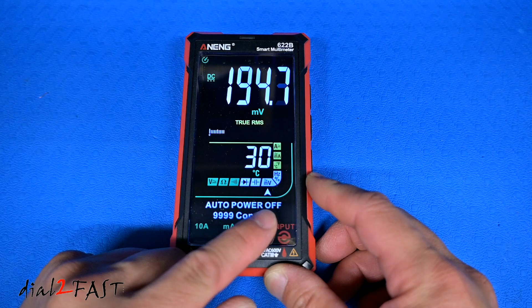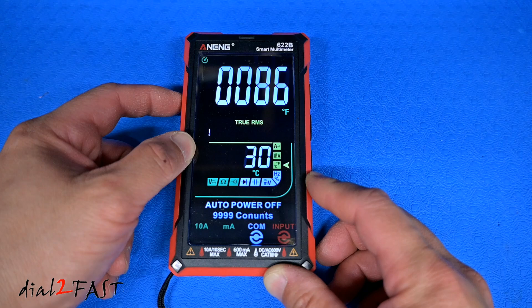If you press the select button on the side, you can switch over to measuring continuity, diode, capacitance, DC millivolt. Press it one more time and now we'll measure AC millivolt. With millivolt measurement, it will measure up to 600 millivolts. Then frequency, temperature, and now we're back to auto.